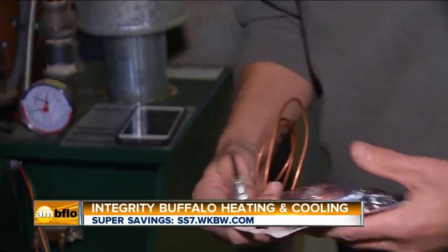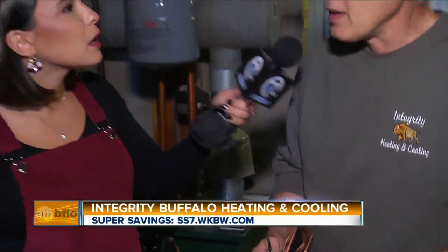What happens is if you don't do your regular maintenance, the orifice can plug up, you can get soot in your boiler, and you also can get CO gas, which you don't want. Is this a common issue that you encounter going into homes throughout western New York? Correct. I check them all, I recommend replacing them all. And I do check for CO gas when I am done — I have a checker to verify that there is no CO gas anywhere near the furnace or boiler.